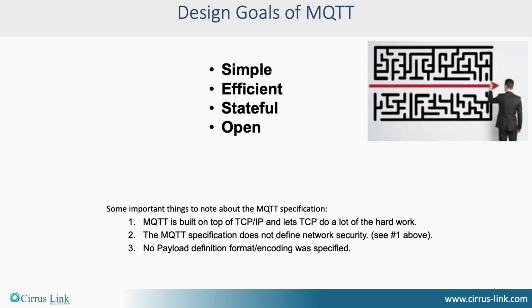The last thing: we didn't define a topic namespace, and we didn't define a payload. I was so tired of register-based protocols that said, oh, in Modbus register 40012 you're going to put this, and oh, a 32-bit floating point, we didn't think about that, but let's magically put 2 Modbus holding registers together and call it floating point. You get the gist, right?